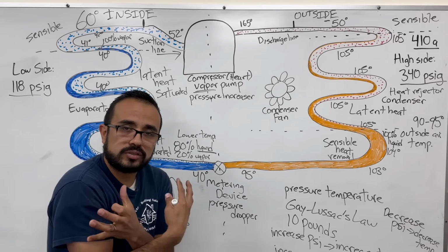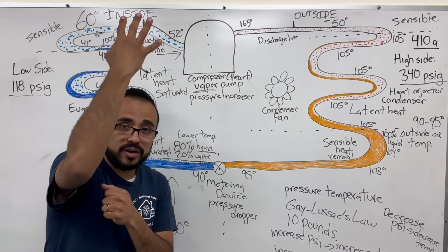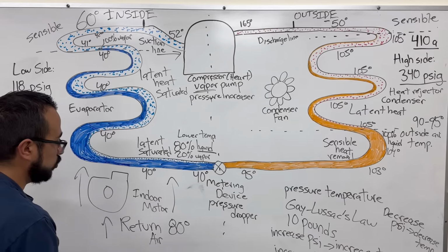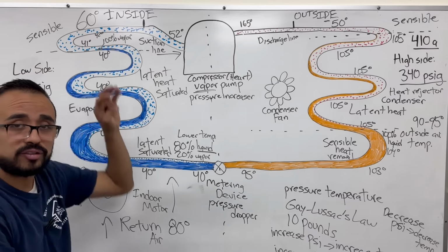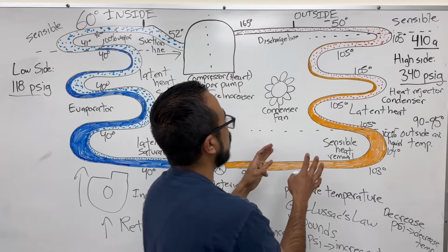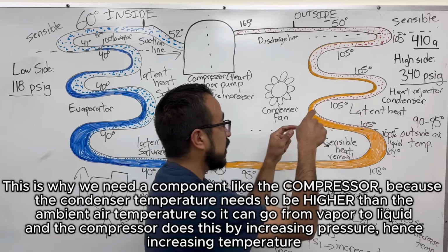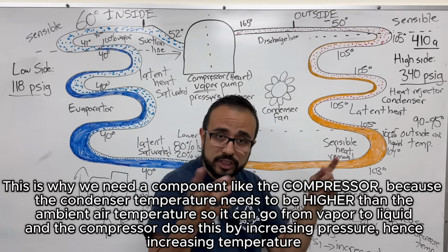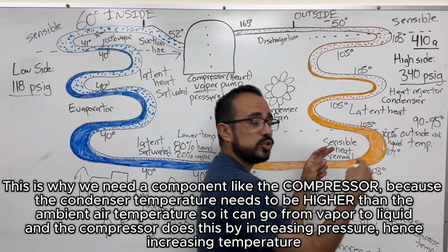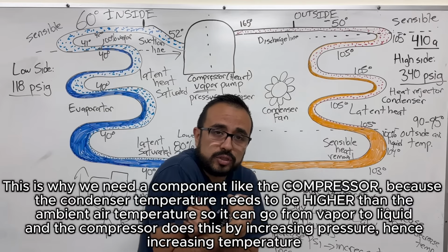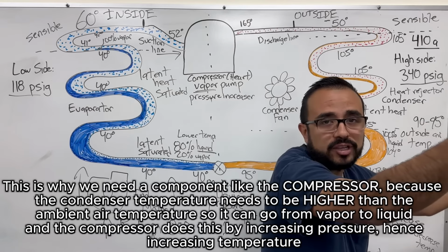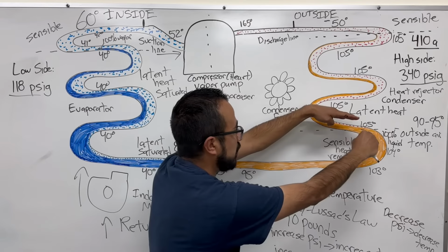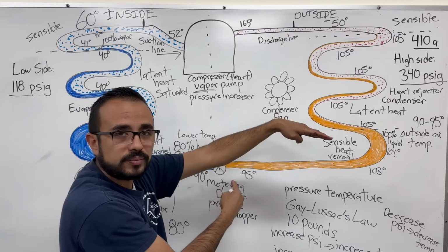Evaporator, it's cold. We need warm air so it can do the heat transfer, boil off the liquid and also turn that 80-degree air to 60-degree air so we can do cooling. On the condenser side, it's really hot. The condensing temperature is hotter than the outdoor air temperature. We need heat transfer. And because the outdoor air temperature is cooler, the condensing temperature gives its heat to the outside air, removing sensible heat, latent heat, and still having that subcooled liquid.